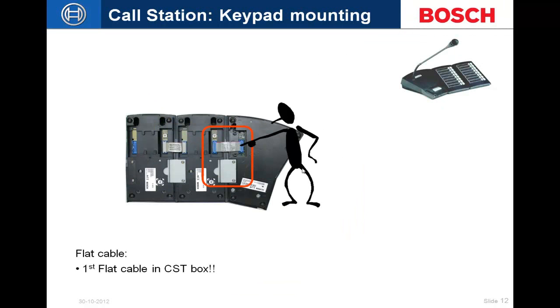An important note: the first keypad ribbon cable comes with the network controller and is a very special cable — it is about a quarter inch longer than the keypad connectors that come with the keypads themselves. If you discard this ribbon connector, you will not be able to plug in your keypads because that extra quarter inch is required. Pay attention when opening your call station — that ribbon cable is located inside that box.